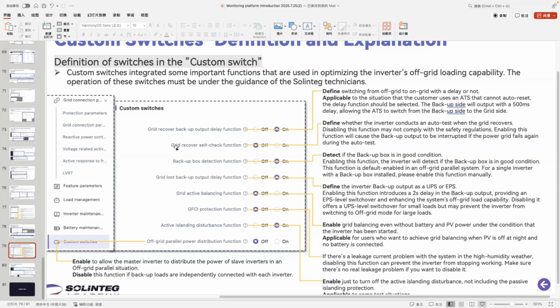Next, the grid recover self-check function: if we turn it off, then when the grid has recovered, the inverter won't enter the self-check status. This function depends on the user's choice. If we turn it on, the inverter will follow the rules set by the safety regulations, but the backup output could be interrupted if the power grid fails again during the auto test.